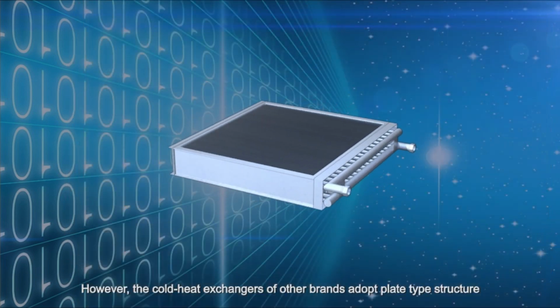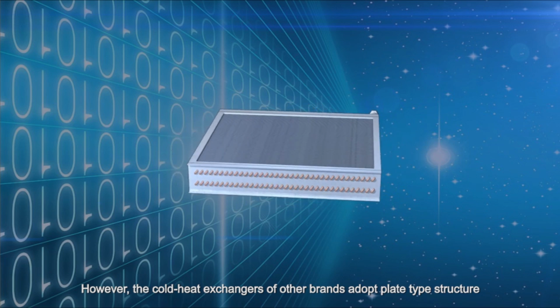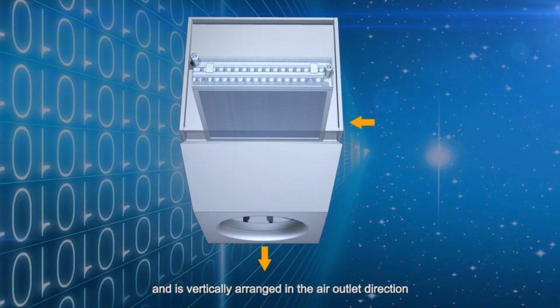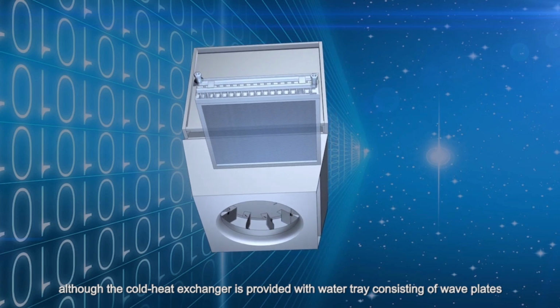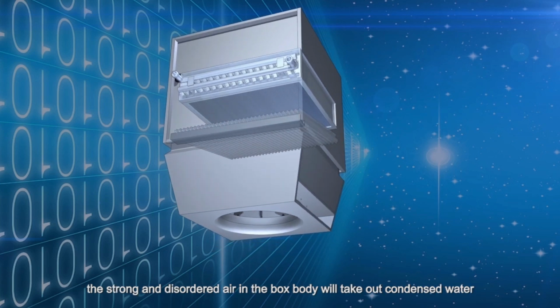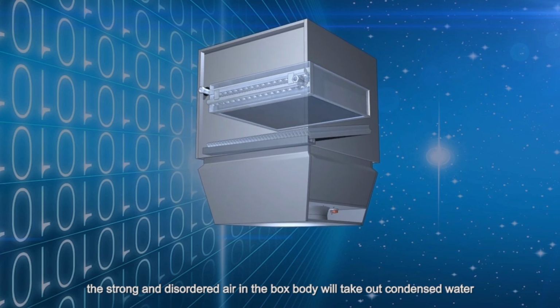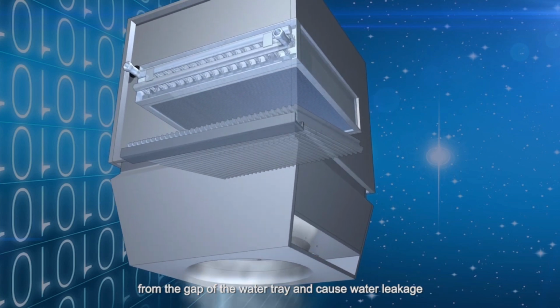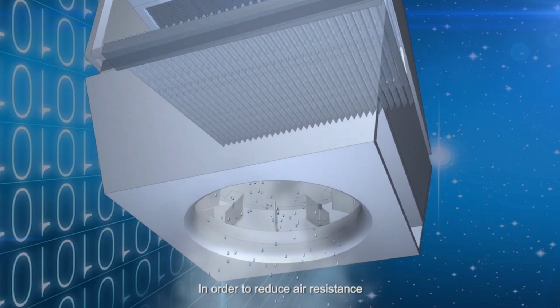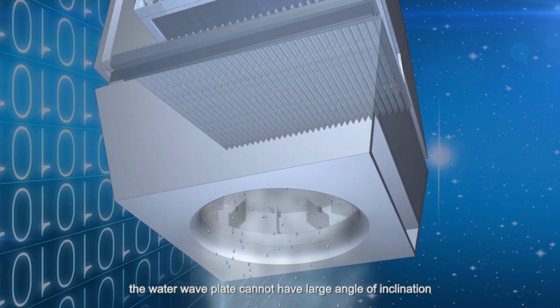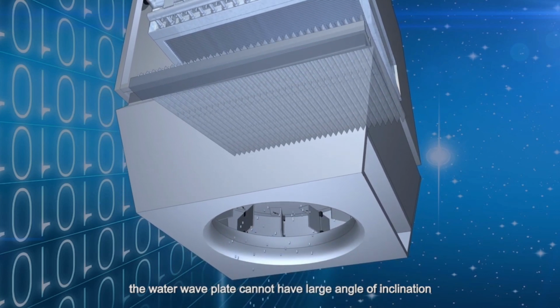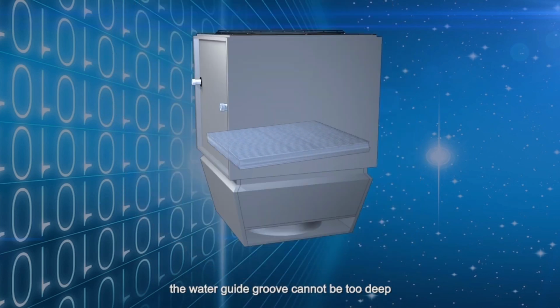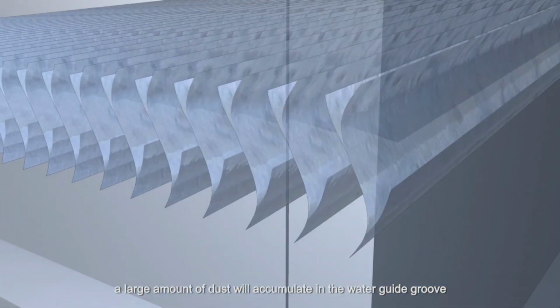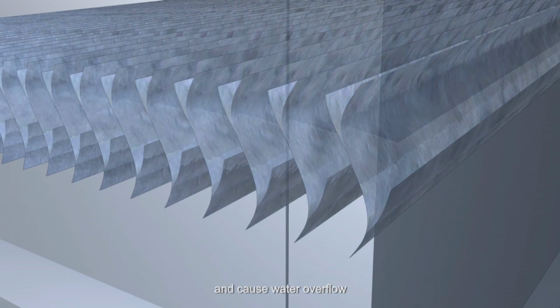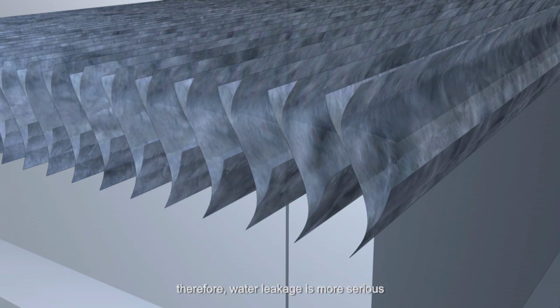However, the cold heat exchangers of other brands adopt plate-type structure and is vertically arranged in the air outlet direction. Although the cold heat exchanger is provided with water tray consisting of wave plates, the strong and disordered air in the box body will take out condensed water from the gap of the water tray and cause water leakage. In order to reduce air resistance, the water wave plate cannot have large angle of inclination. The water guide groove cannot be too deep, and after using for a certain period, a large amount of dust will accumulate in the water guide groove and cause water overflow. Therefore, water leakage is more serious.